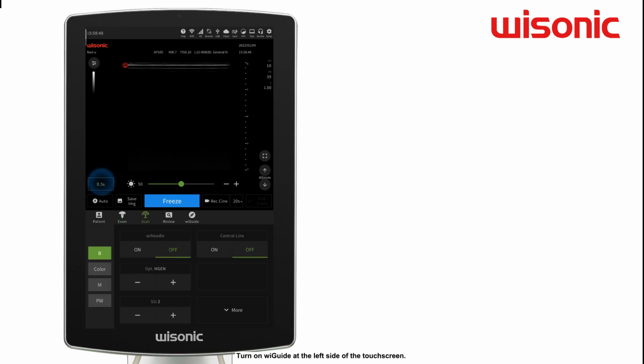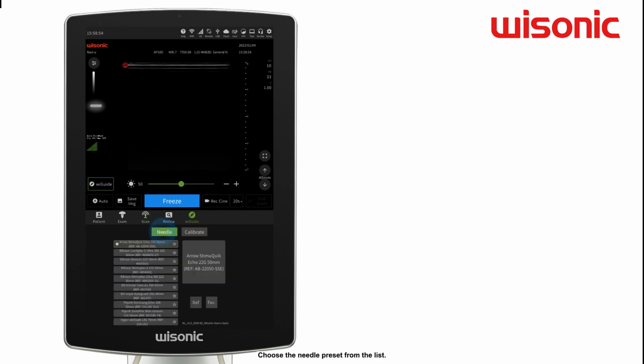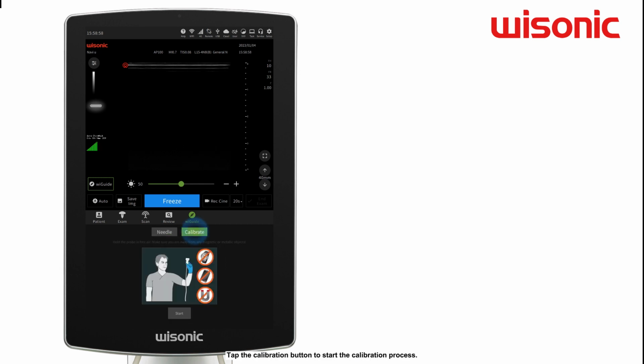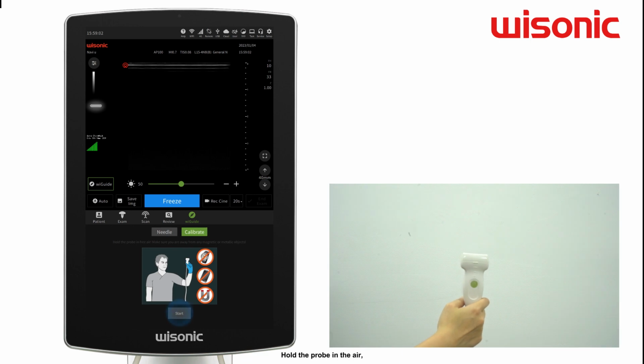Turn on wiGuide at the left side of the touchscreen. Choose the needle preset from the list. Tap the calibration button to start the calibration process. Hold the probe in the air, press Start, and wait for a few seconds until the system indicates the process has completed.